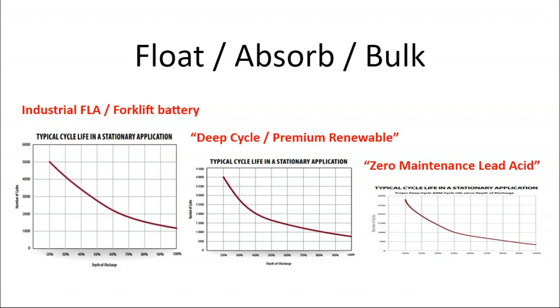It's called an equalization charge, because by overcharging those batteries you can provide some power conditioning to keep them in good, healthy shape. The danger is that applying too much voltage to a battery can break it entirely. So for the same reasons, you have to be more careful about rapid charges and overcharging with sealed batteries.